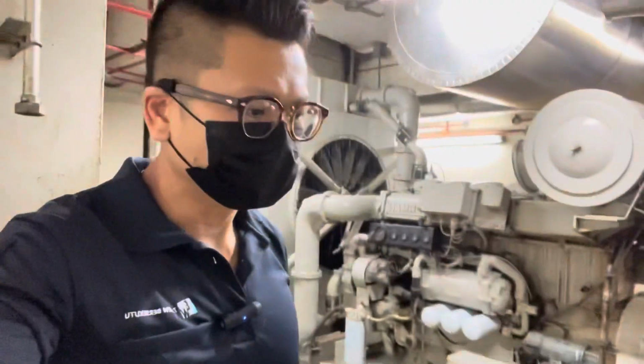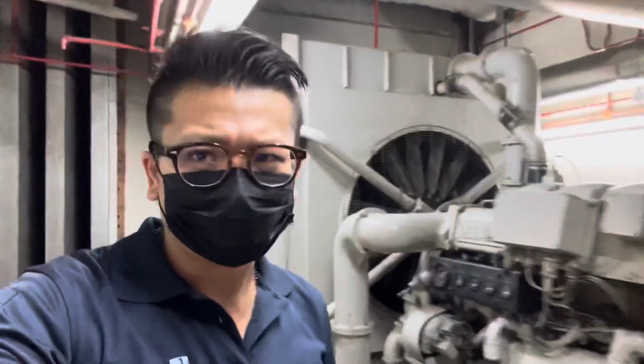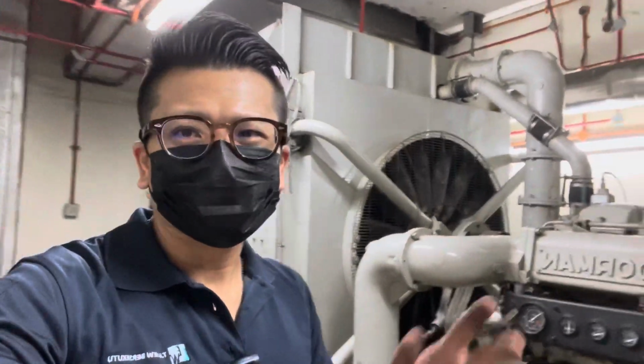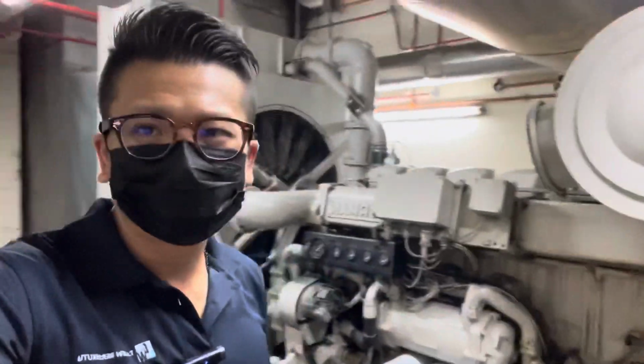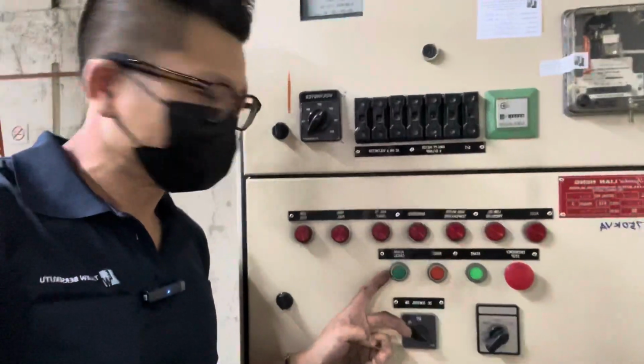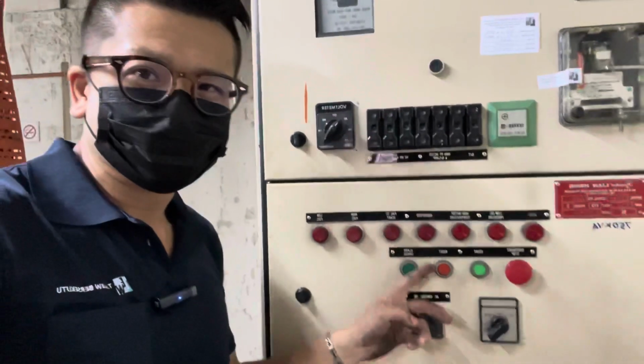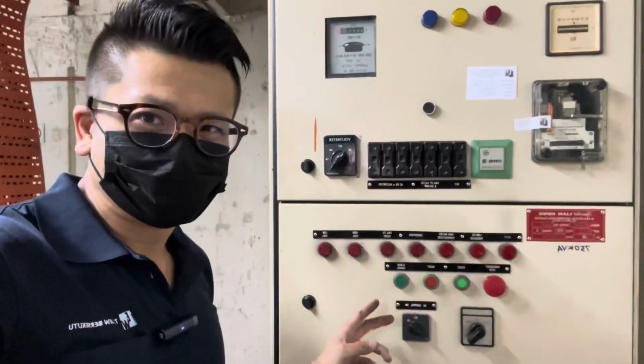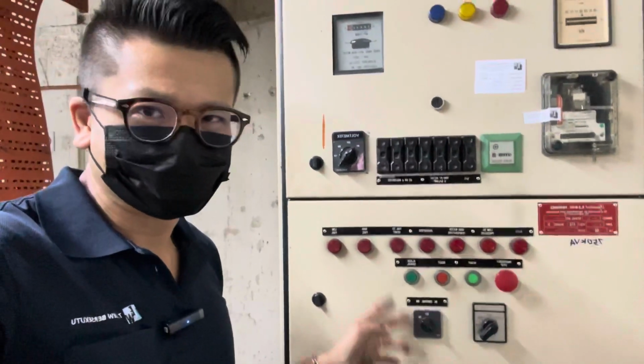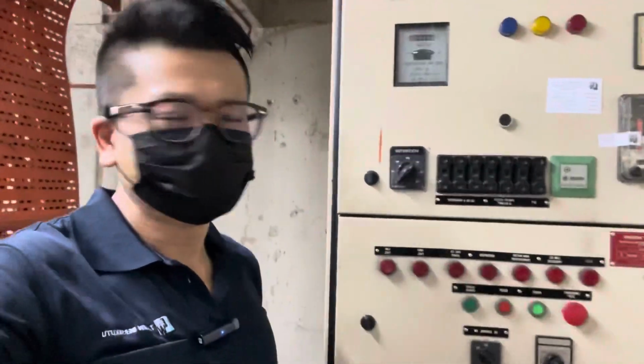Okay, after 5 minutes, the genset stopped automatically, and that proved that under auto mode, it can start automatically and can stop automatically. This is the most important thing because during TNB power interruption, we don't have to come here and manually turn it on. Okay, this is how the system is supposed to be. So nothing is an issue, only that previously this is the button I pressed, alarm cancel and reset. Afterwards the genset is back to normal condition. It can start manual and it can start auto and now can stop automatically.